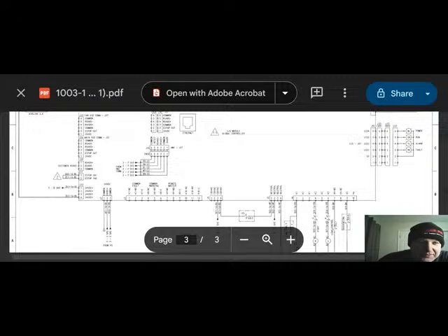So if you're coming in on common, coming out on normally closed, basically what that means is when this machine is off, you're going to have power flowing out this wire here, or when this machine faults, you will have power flowing out this wire here, and then when they open it, do the opposite. So if this machine is sitting here off, this is a dead contact, machine powers up, this powers up, and then when the fault comes along, this will go away.